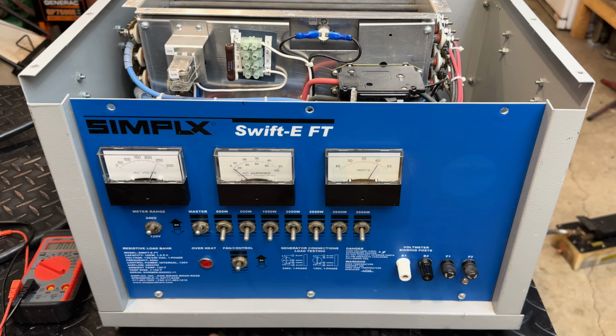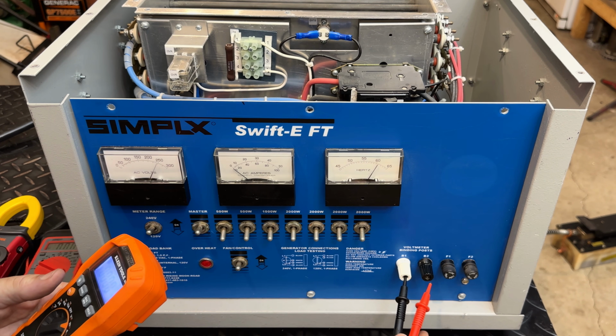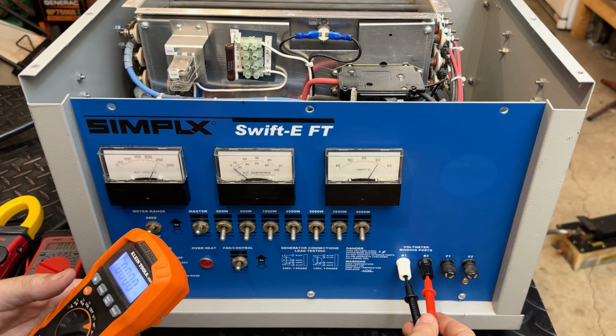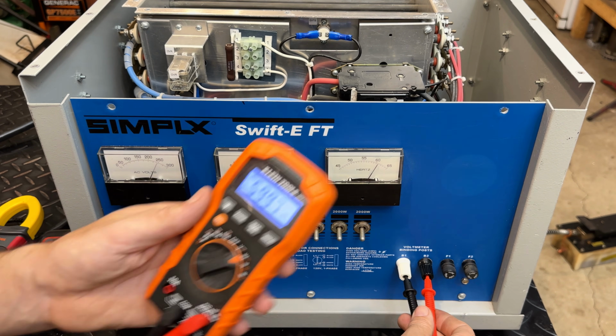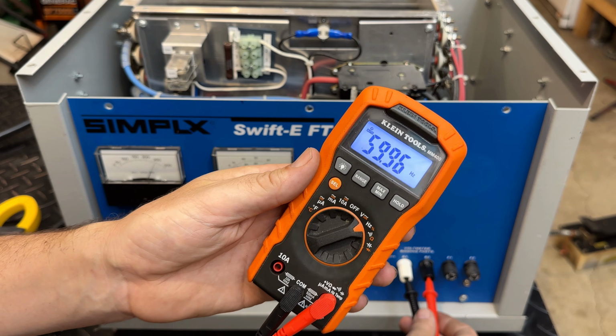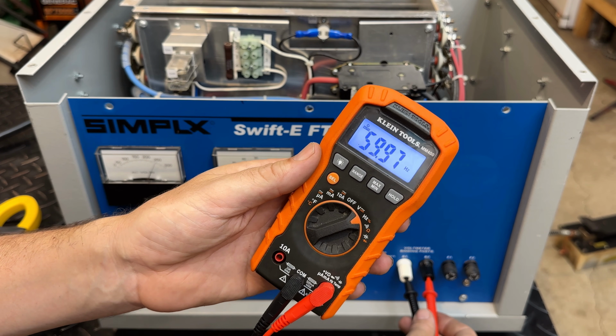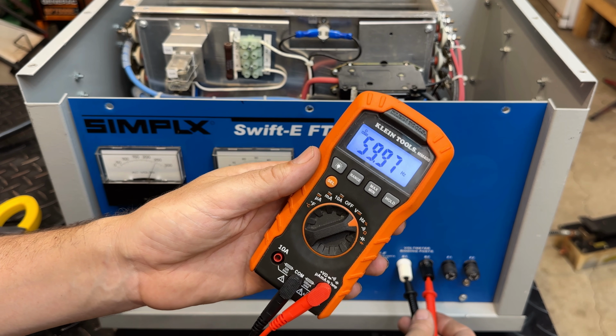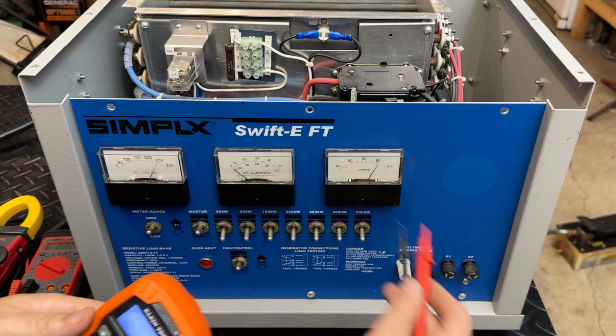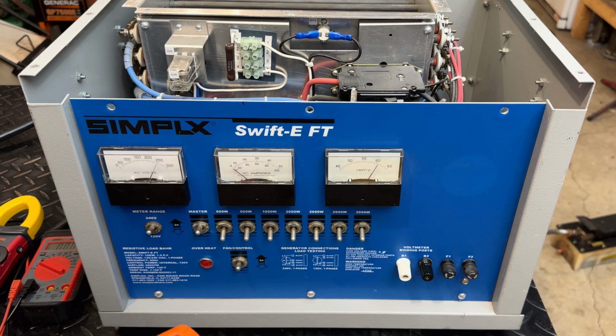Let's double check the hertz. The hertz are a little bit off as well. We are just about at 60 hertz, or at 59.97, and this gauge is saying we're closer to 60 and a half. So again, not a big deal, but it's something to keep in mind and potentially adjust if we can.